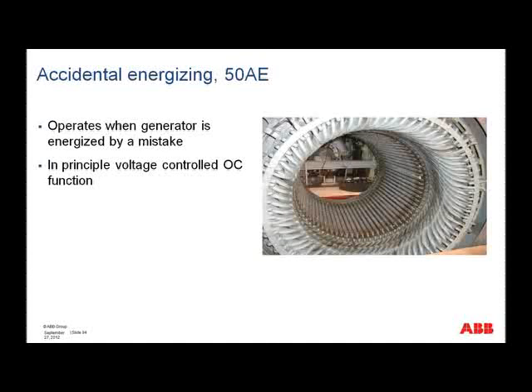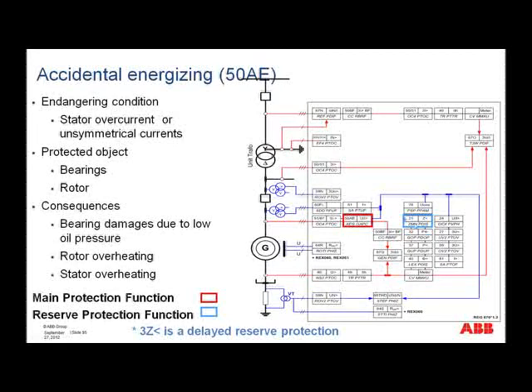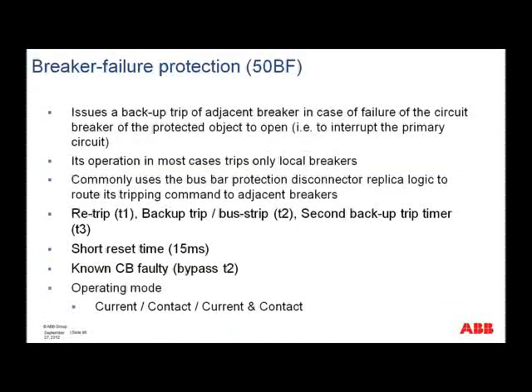We have accidental energizing, okay, which operates when the generator is at standstill and is then energized by mistake. So here also in our protection package, we have this function for the accidental energizing. Breaker fail protection. This, of course, is protection that will be informed that a trip has been sent to the circuit breaker, and then it will determine whether the circuit breaker in fact opened or not. It can make this determination by seeing that the current reset, or as well as the current, you can use the auxiliary contact, and it would see that the breaker opened by monitoring that the auxiliary contact changed state from closed to open position.